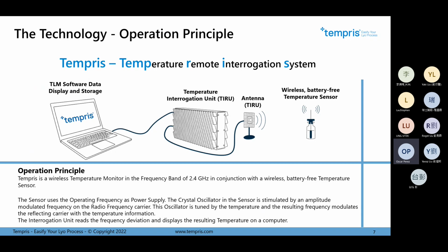The technology works as follows. The main interrogation unit generates a radio frequency signal between approximately 2.4 and 2.5 gigahertz, and radiates this radio frequency via the interrogation antennas. These antennas can be installed inside or outside. Normally, we always prefer inside the freeze dryer chamber. But we also have small applications, lab and pilot freeze dryers, which have a side glass or acrylic door, so we can also use external antennas. The radio frequency goes through the antennas and radiates inside the chamber to reach the sensors. The sensors also have a very thin stainless steel antenna, which catches this signal and brings the energy to the sensor.